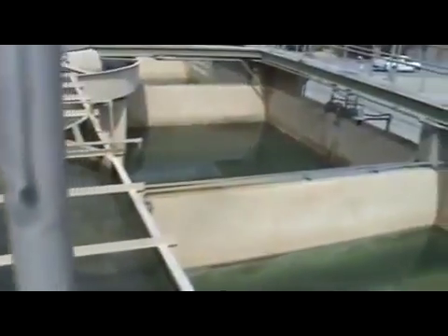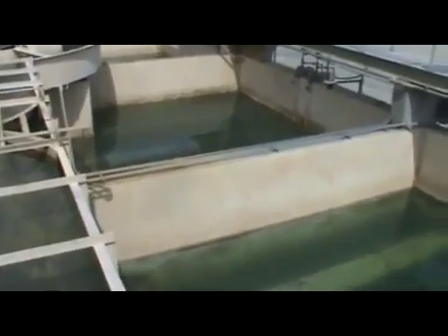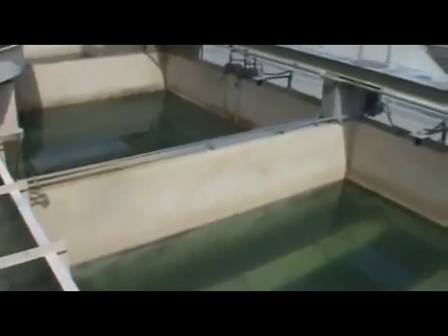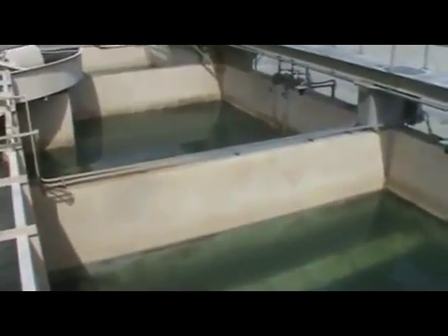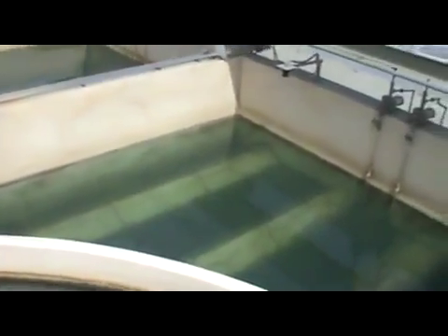There are generally three things that we use to determine when it's time to backwash a filter. The time that filter's been running, or you could think of that as the gallons that filter has produced. Turbidity, if the effluent turbidity starts to rise a little bit on that filter. Or head loss. When I talk about head loss, I mean the filtrate, the water coming out of the other side, starts to slow down. It's not as great. And basically you can see that by the water level inside the filter beginning to rise.